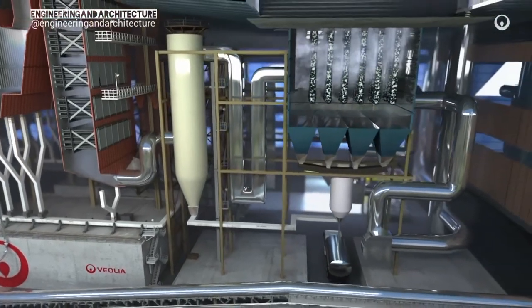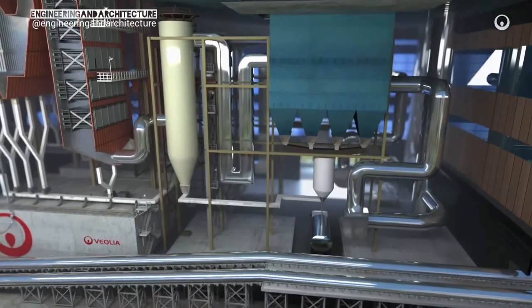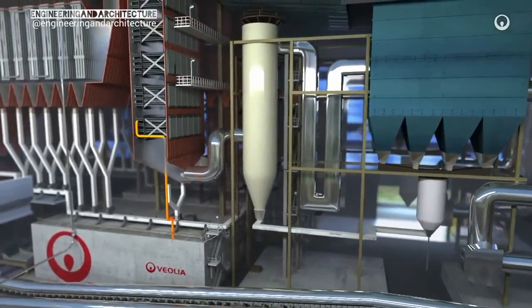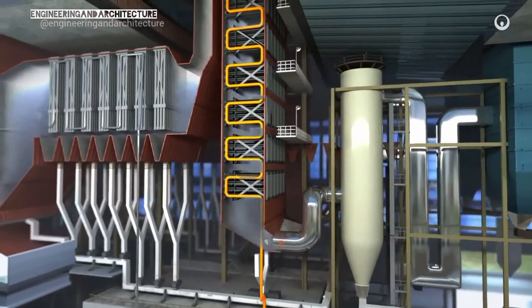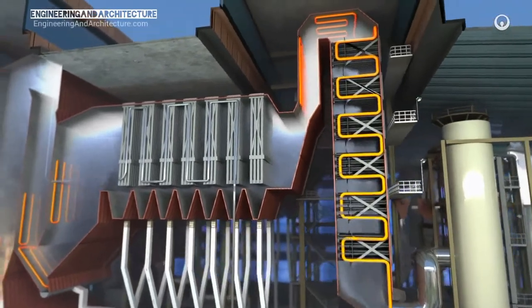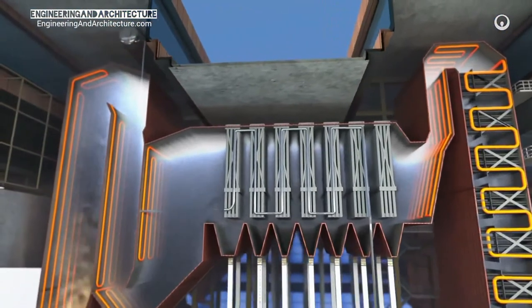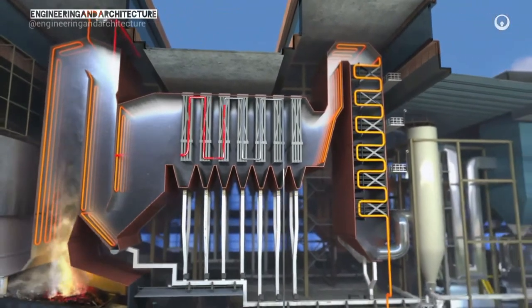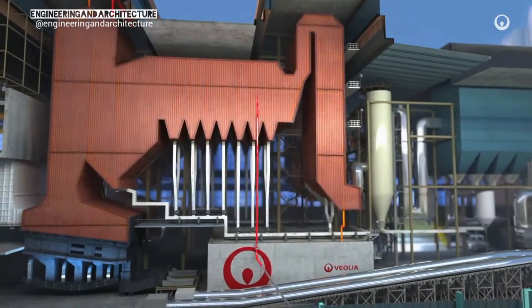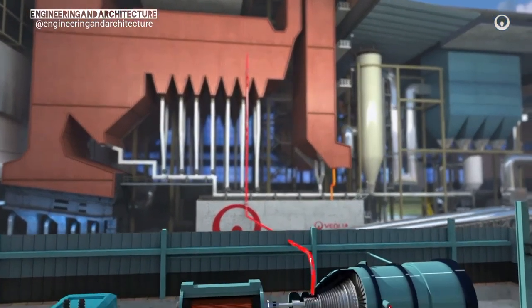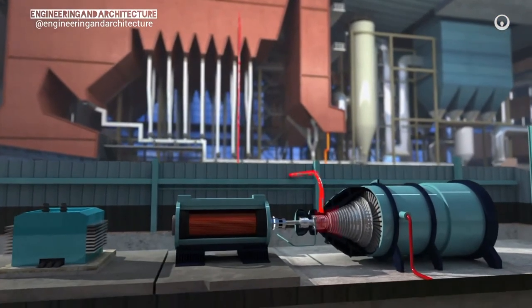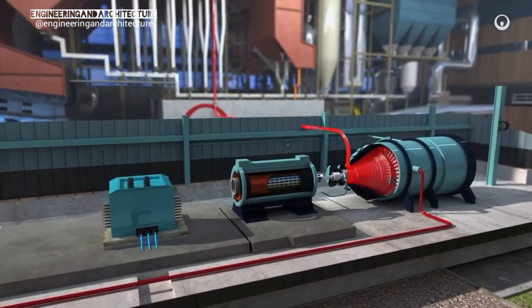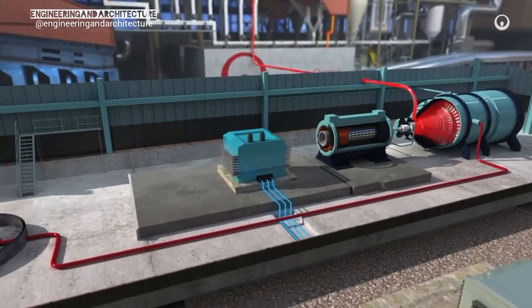The acids in the off-gas are neutralized in a reactor by injecting lime and sodium bicarbonate, to which activated carbon is added to absorb dioxins and heavy metals. Bag filters retain dust, salts, and other solids which will be sent to a hazardous waste landfill. The incineration of waste generates energy which is now recovered: heat is captured by water tubes in the boiler walls, heated water is converted into high-pressure steam, superheated in high-temperature exchangers, and sent to a cogeneration plant. This steam drives a turbine coupled to an alternator to generate electricity fed into the public grid.